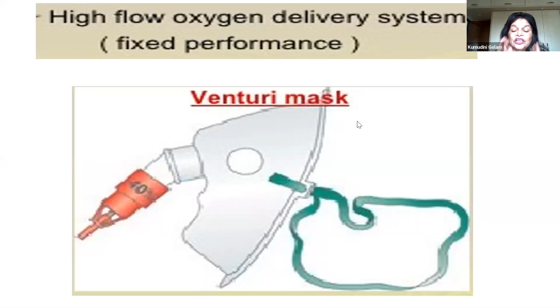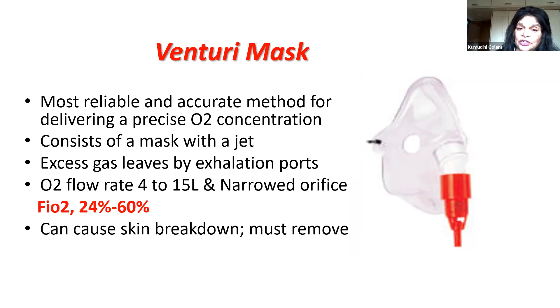It consists of a mask with a jet. Now this, you see, is a jet, and we know how the Venturi principle works with the jet. Excess gases leave by the exhalation ports, and with oxygen flow from 4 to 15 liters and a narrow orifice, FiO2 will be anywhere between 24 to 60%. But it can cause skin breakdown, so you have to take care when you put this mask on a patient's face.